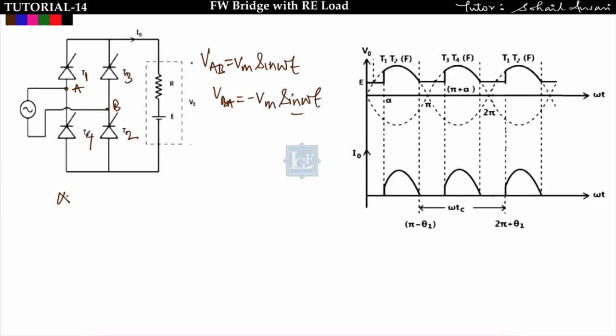We must trigger the thyristor after angle θ, where θ is the angle at which the supply voltage equals E — that is, θ = sin⁻¹(E/Vm). This was already explained in the half-wave controlled rectifier for RE load: if we trigger T1 and T2 before θ, they are in reverse bias and won't conduct. So the triggering angle must be greater than or equal to θ. Here we trigger at ωt = α, where α > θ.